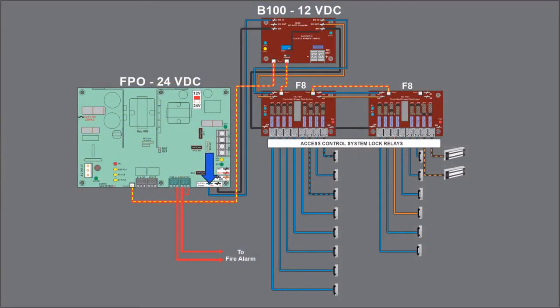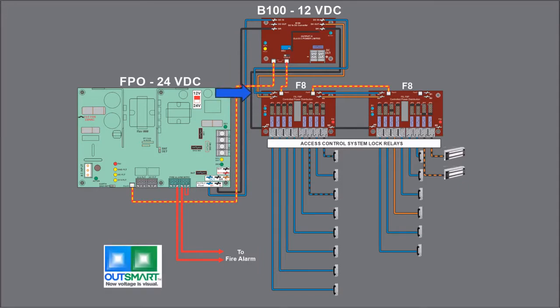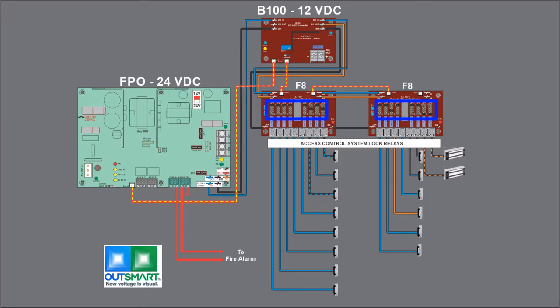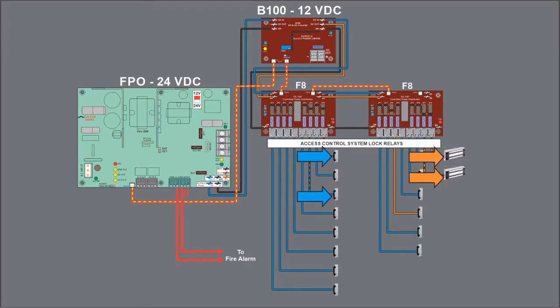Connect DC1 of the FPO to DCIN of the B100. Connect B1 of the F8 daisy chain to the second DCIN terminal of the B100. Connect B2 of the F8 daisy chain to DC out of the B100. On the F8, program the lock outputs to 12 volts or 24 volts as necessary and the locks to drop out on fire alarm. Each lock now has a fuse in series with it, can be controlled by the access system door relays, and the egress locks will drop out when the fire alarm is activated.